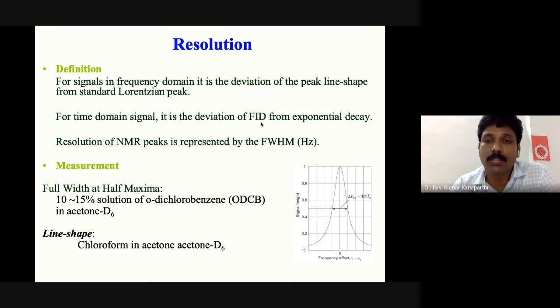Normally the experiment is done and the spectrum is represented in frequency, so you can give the unit of the resolution as hertz. And experiment-wise, how do we measure it? This is very important. Why? Because certain times we have to calibrate the instrument, because that is related to the correctness of the instrument. So sometimes we measure and we calibrate the instrument. So how do you basically measure the resolution of the instrument?